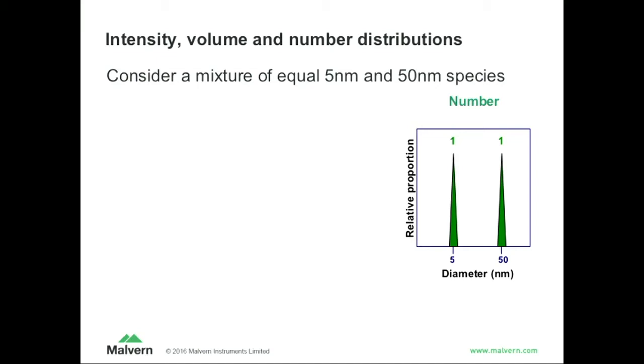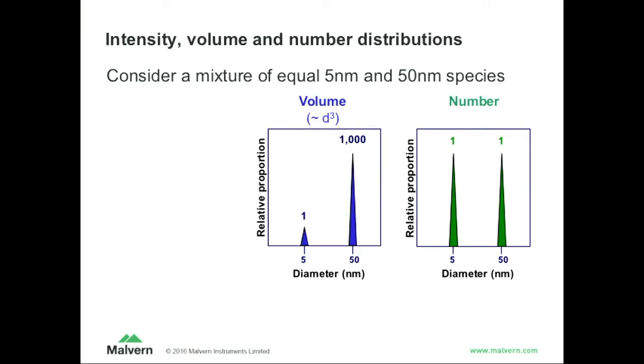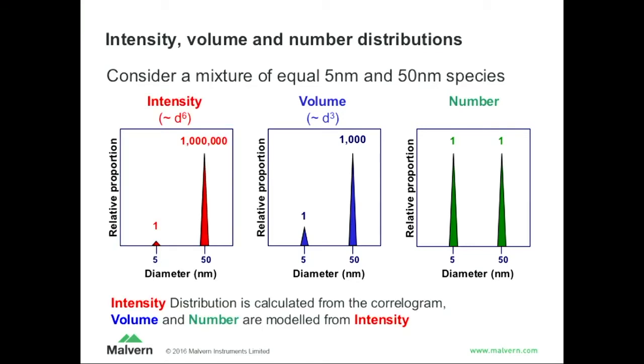Let's do a little thought experiment. We have 50% of 5 nanometer and 50% of 50 nanometer particles here. If you do a number distribution, you see these two nice even peaks, 50-50. But people tend to think in terms of concentration — how much material do they have. The concentration is proportional to the volume, so it's proportional to size to the third power. Now all of a sudden you have a thousand times as much material from the bigger things than from the small things. And if we look at scattering intensity, it's proportional to size to the sixth power, so our 50-50 in number has turned into a 1 million to 1 in light scattering. The tricky thing is that when we do light scattering, we start out with the intensity distribution. The safest approach is to always stick with the intensity if you're doing dynamic light scattering, because that's the native way of doing this.